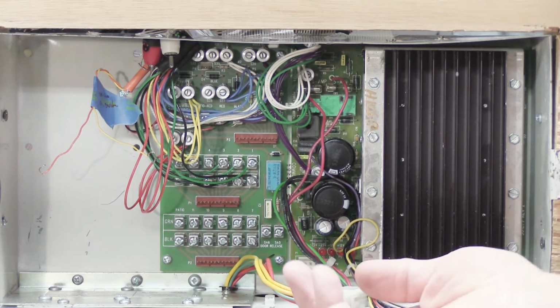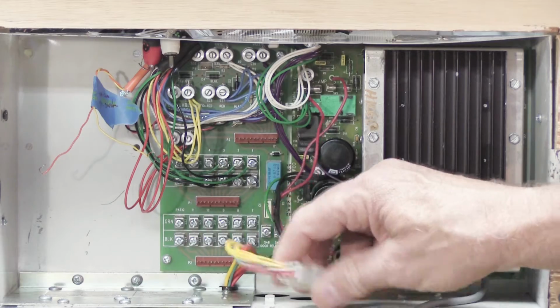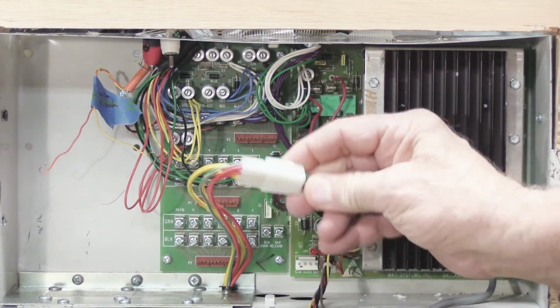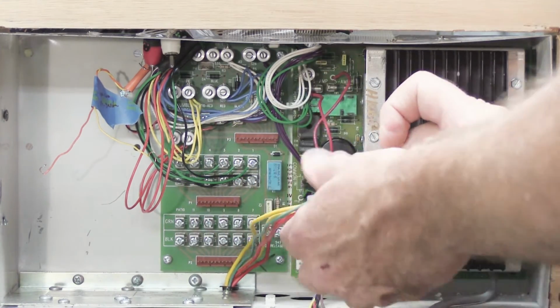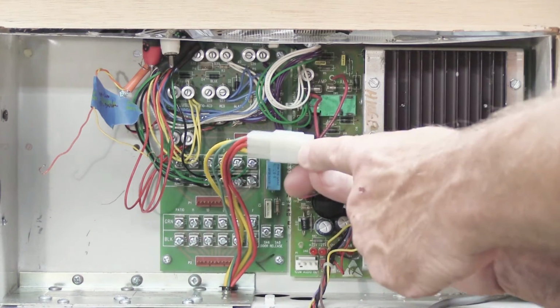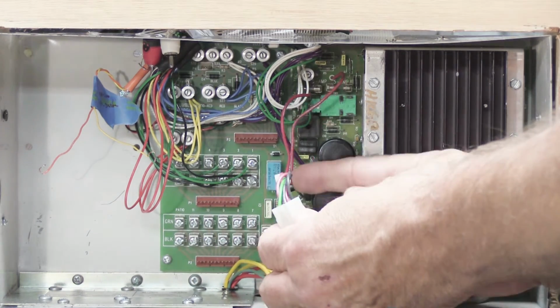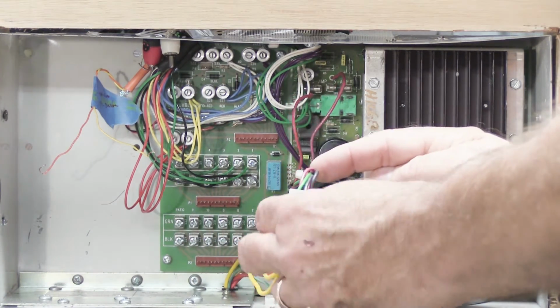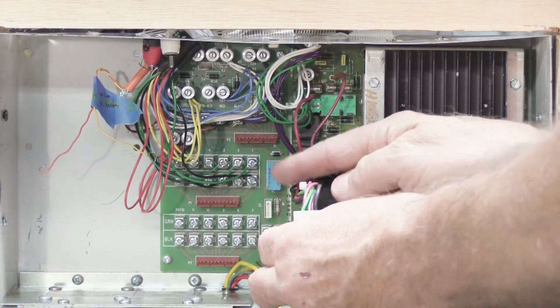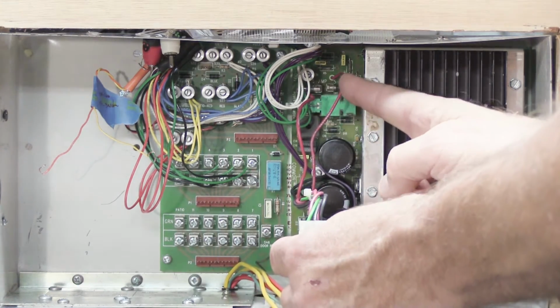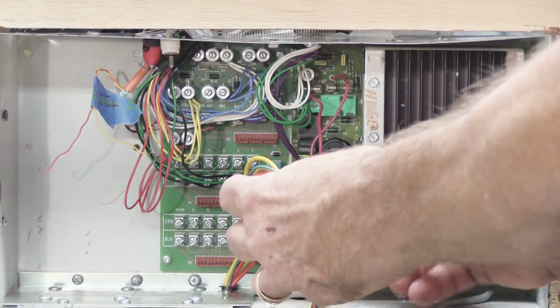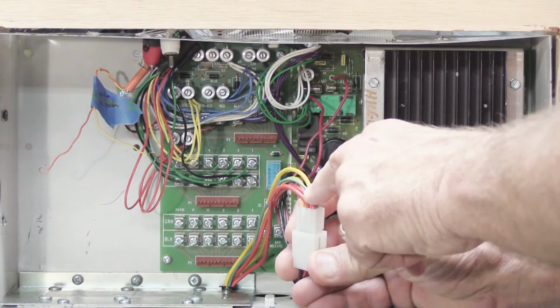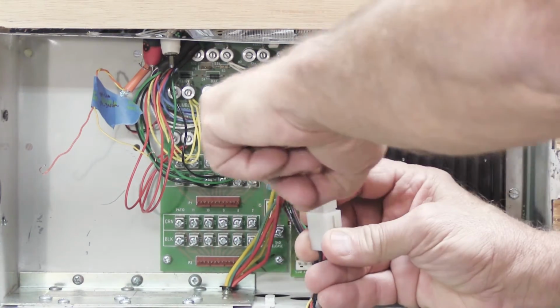One of the things we have to do is unplug the amplifier power supply module from the transformers. This big white connection has wires here, which are 2 red, 2 black, and a green, and they go to the amplifier power supply module up here. On this side, you have 2 yellow, 2 red, and a green, and these are the wires that come from the transformers down below the plate.